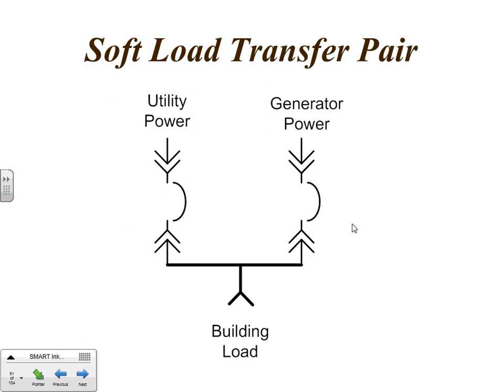And it can operate that way, again, for utility curtailment programs. They'll be synchronizing in both directions. So when the utility says, we want you to run your generator sets, the customer would start the generator and it would synchronize to the utility going to emergency. Then as soon as it was synchronized, the generator breaker would close and then the utility would open. Again, the load didn't know anything happened. And the reverse, the same process going back when the curtailment interruption is over.